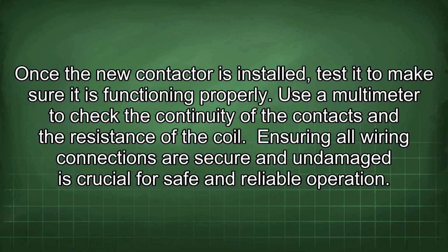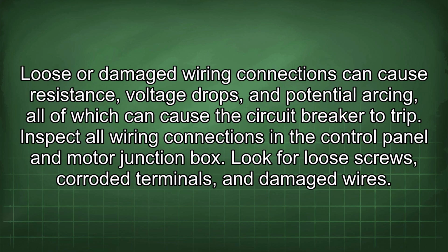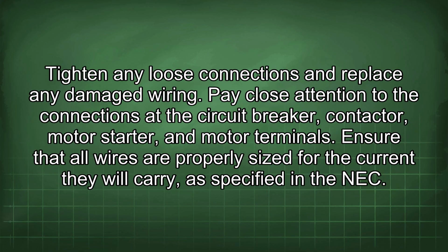Ensuring all wiring connections are secure and undamaged is crucial for safe and reliable operation. Loose or damaged wiring connections can cause resistance, voltage drops, and potential arcing, all of which can cause the circuit breaker to trip. Inspect all wiring connections in the control panel and motor junction box. Look for loose screws, corroded terminals, and damaged wires. Tighten any loose connections and replace any damaged wiring. Pay close attention to the connections of the circuit breaker, contactor, motor starter, and motor terminals. Ensure that all wires are properly sized for the current they will carry, as specified in the NEC.